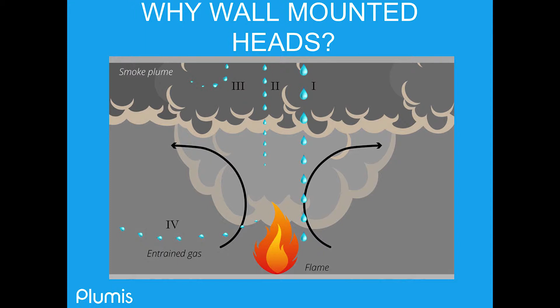When we're talking about water mist, the mist molecule is very, very small. And so it doesn't have very much momentum after it leaves the nozzle, and so it moves around on the air currents that are in the room. The air currents actually come into where the fire is. It's called entrainment, and it comes into the base of the fire. And the water molecule is brought into the fire by the air molecule, or by the air vents and the entrainment that's coming in. And so it actually helps. It cools the fire, puts the flaming fire out, and actually, through the expansion, eliminates the oxygen for the flaming fire. So this is basically how we are a little bit different.